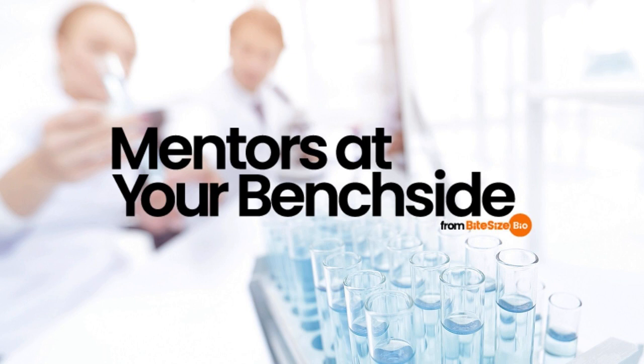Ideally, you should use standard weights to do this, but if you're stuck, you can improvise, so you can measure out 75 milliliters of water, for example. But be aware that not having a sample of known weight means that you'll be able to spot random error, but not systematic error. Please note that your sample must have reached thermal equilibrium before it is used. And whatever you're using will be referred to as the sample here.